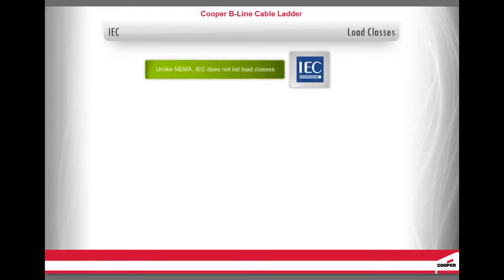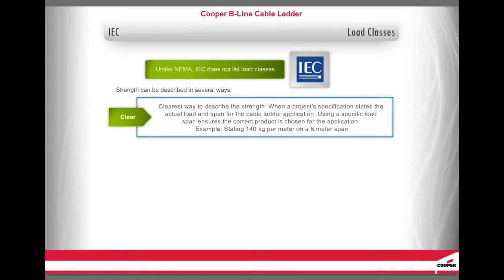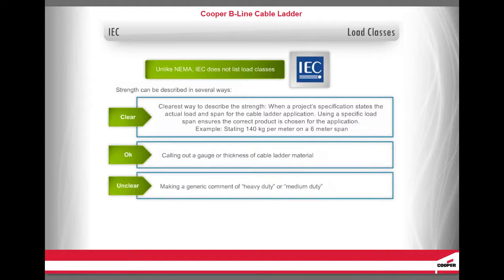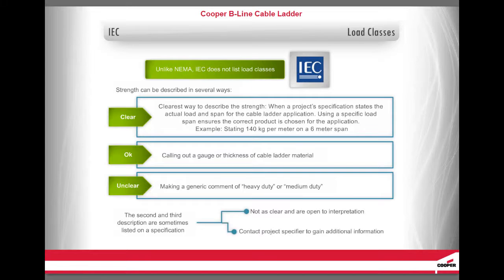Unlike NEMA, IEC does not list load classes. In the IEC specifications, the strength can be described in several ways. First, the clearest way is when the project specification states the actual load and span for the cable ladder application — for example, stating 140 kg per meter on a 6-meter span. Second, calling out a gauge or thickness of the cable ladder material. Third, making a generic comment of heavy duty or medium duty. The second and third descriptions are sometimes listed on a specification but are not as clear and are open to interpretation. In this situation, it would be best to contact the project specifier to gain additional information.